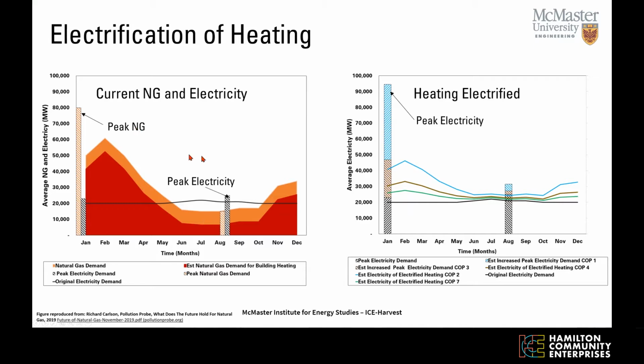Now let's electrify heating. I won't get into this too much, but we have different COPs. Here's our average COP for, say, an air source heat pump with a seasonal average of 2. Here's an average COP of 3, typical of an installed ground source heat pump. And here's a higher one, a COP of 7.